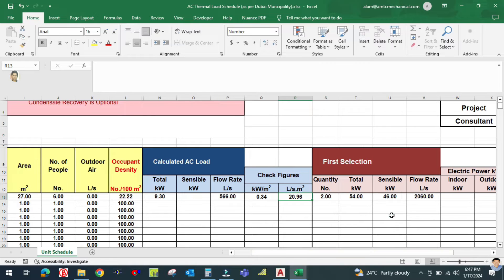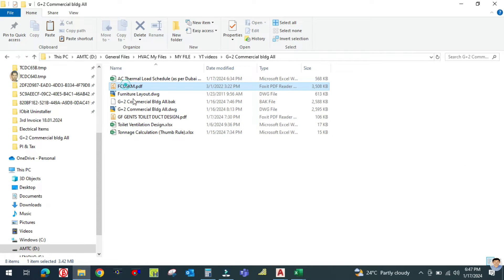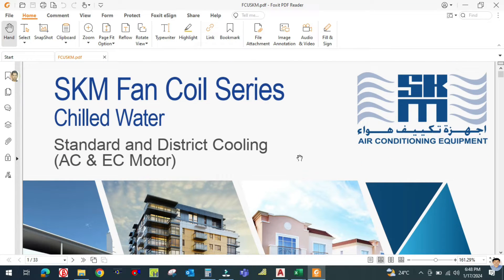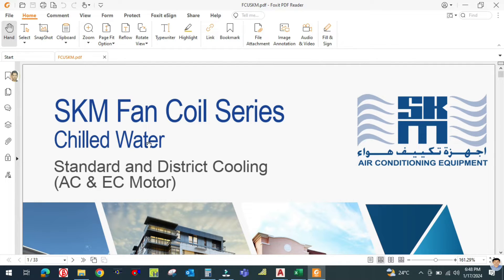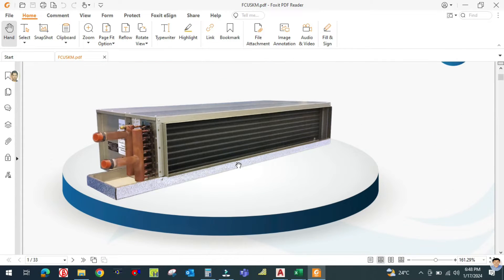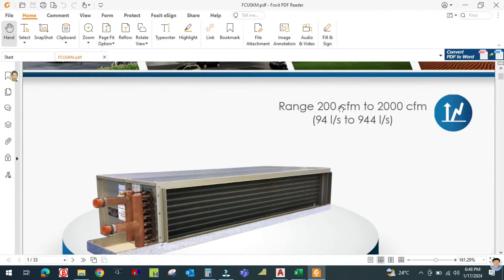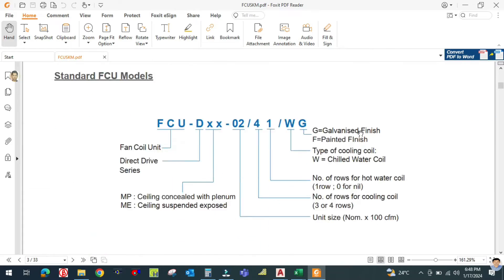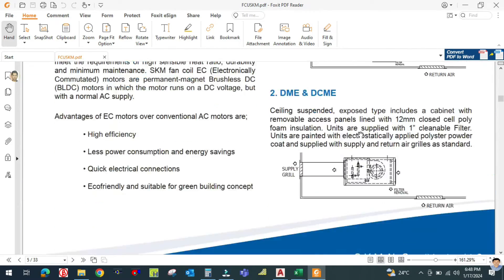For the first selection, you select the AC unit from a catalog. One of the AC brands approved for Dubai is SKM Air Conditioning. This is their catalog for chilled water fan coil units, with a range from 200 CFM to 2000 CFM. Let us go to the selection data and capacity rating sheet.